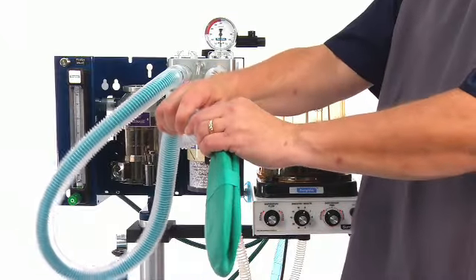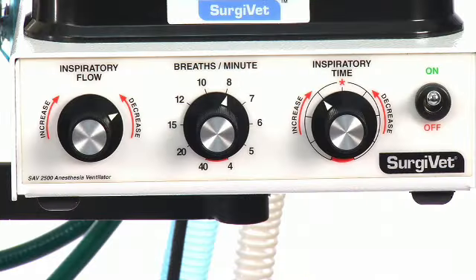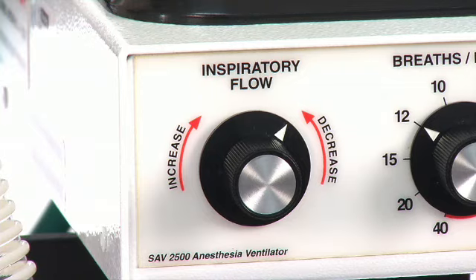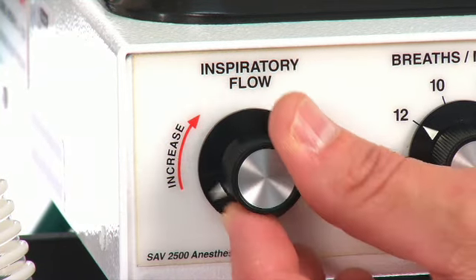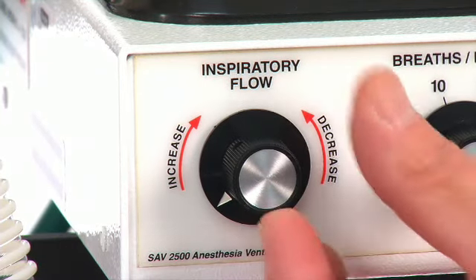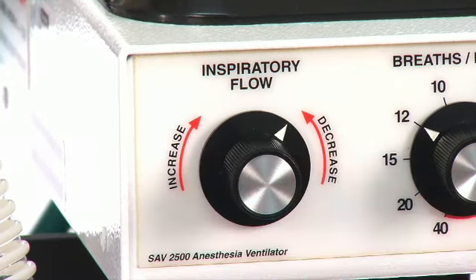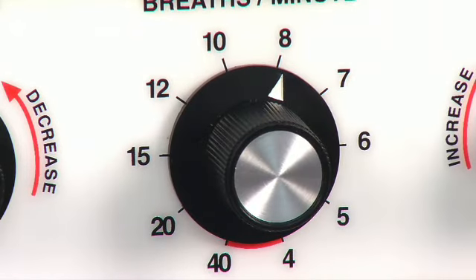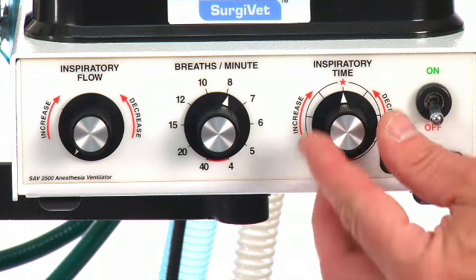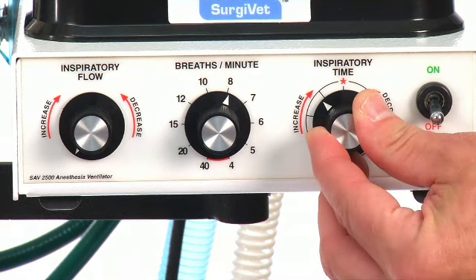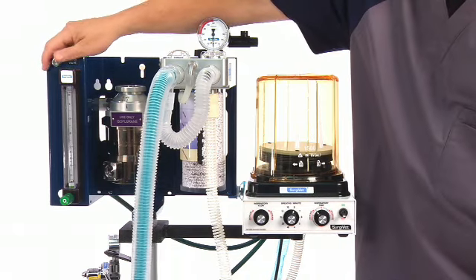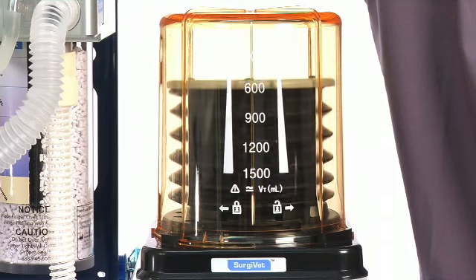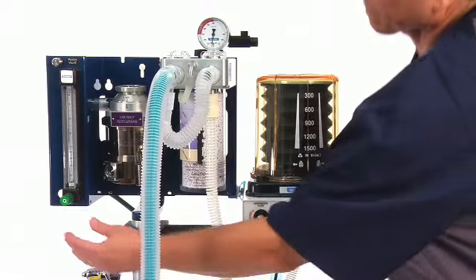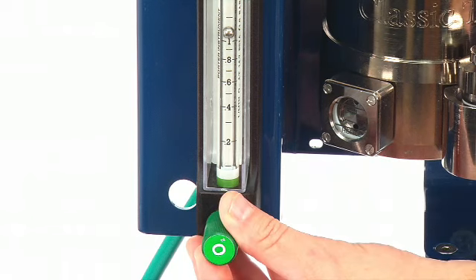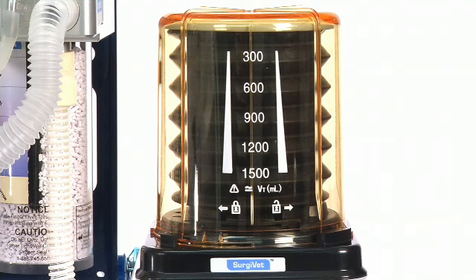Connect the test lung to the patient F circuit. For initial startup settings, turn the inspiratory knob all the way counterclockwise and then turn clockwise a quarter turn. Set the breaths per minute to 8 to 10. The inspiratory time should be set just left of center. Completely inflate the bellows using the oxygen flush valve, and then turn your flow meter knob to deliver 1 liter per minute. The bellows should hold in the full position.